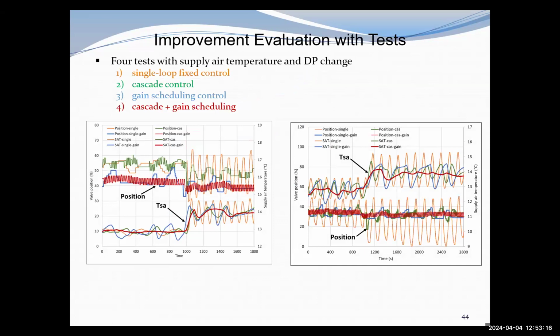So we did the test to compare the performance of all these different control strategies: single loop fixed gain control, cascade control, gain scheduling control, and the cascade plus gain scheduling control, on the higher load condition and the lower load conditions. The left figure shows the response under the higher load condition, and the right figure shows the result under lower load conditions. We can see here the yellow, or orange, curve shows the loop response with the single loop fixed gain control, the green curve shows the cascade control, the blue curve shows gain scheduling control, and the red curve shows the cascade plus gain scheduling control.